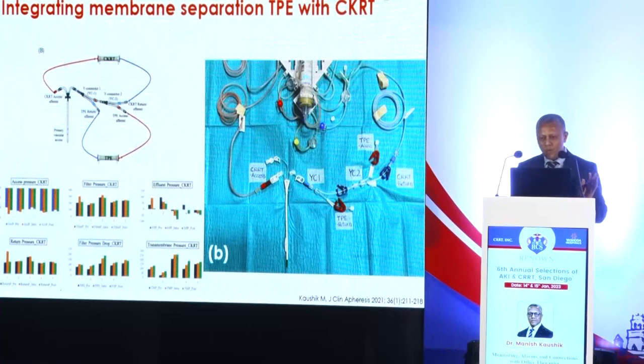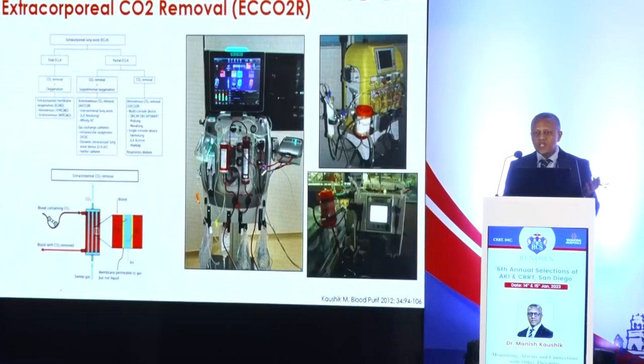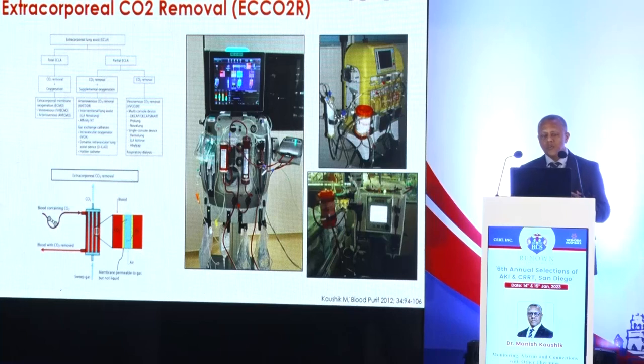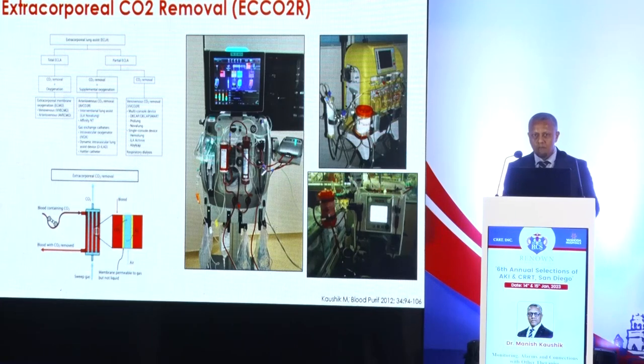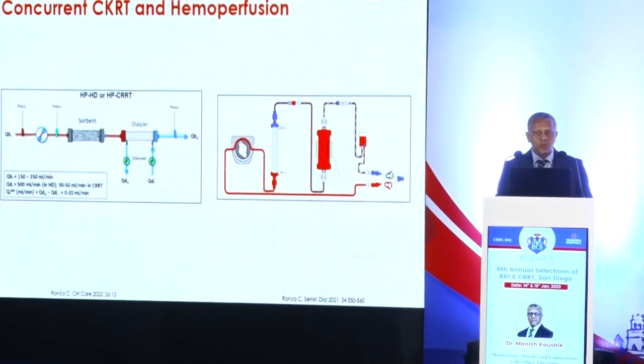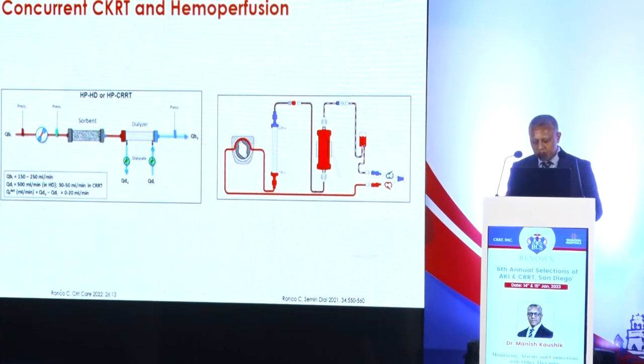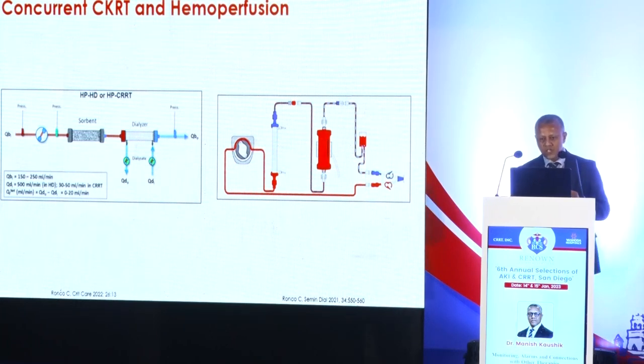Extracorporeal CO2 removal is increasingly used and can be done independently or integrated with the CKRT circuit — many modern platforms allow multiple therapies to run together. Lastly, hemoperfusion columns are used in patients with sepsis, post-cardiac surgery, hyper-inflammatory states, or high cytokine release situations, and these cartridges can be integrated into the CKRT machine. With that, I will stop here — thank you very much.